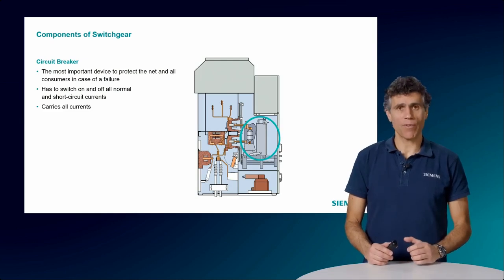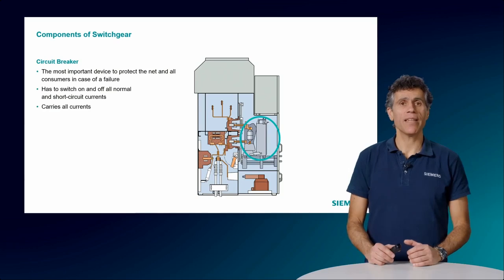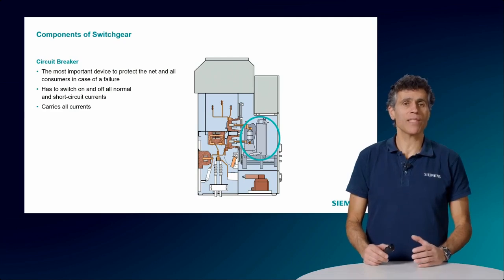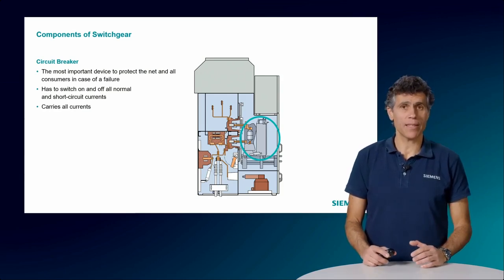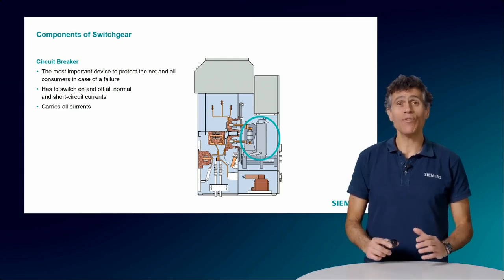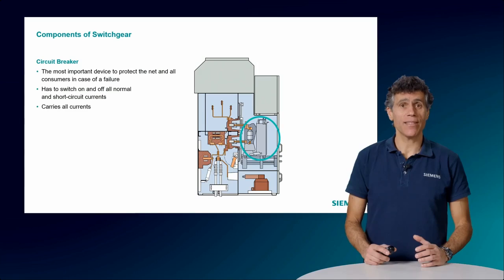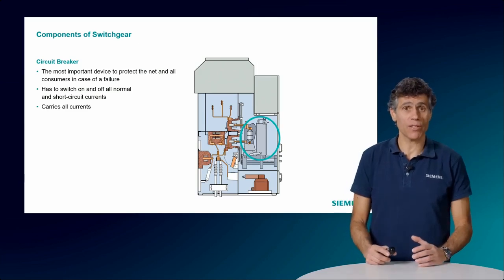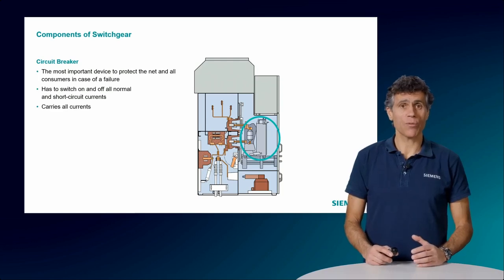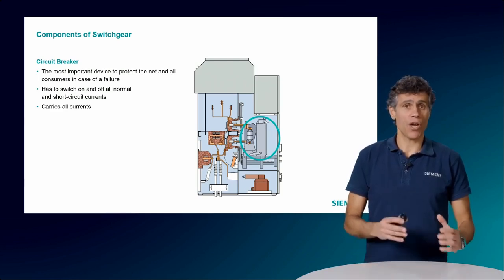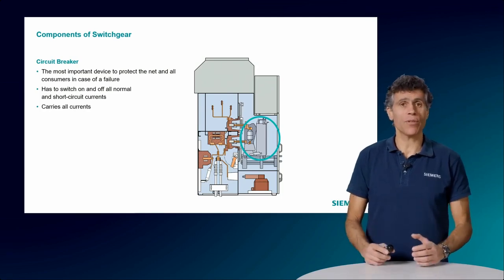But there is another mode of operation which is much more demanding than that one, which is the disturbed service. In this case, the operation takes place under faulty conditions, which occur rarely due to some failure, like for example when a small animal enters the switchgear. In those situations, huge currents can flow through the switchgear or the voltage can increase tremendously. The current can reach more than 100 times its normal operation value, and the circuit breaker must be able to switch those currents off. A medium voltage circuit breaker is also capable of switching on and off in faulty conditions.